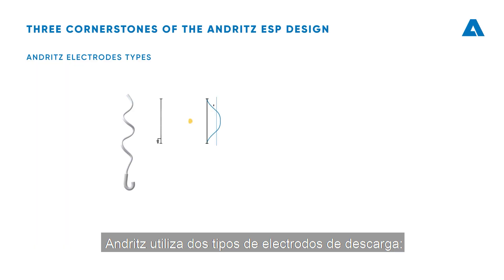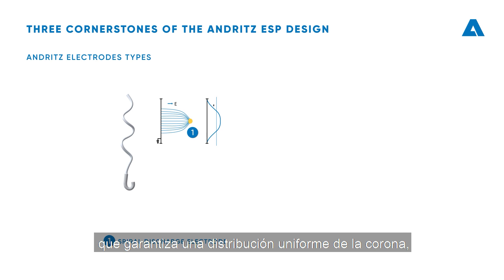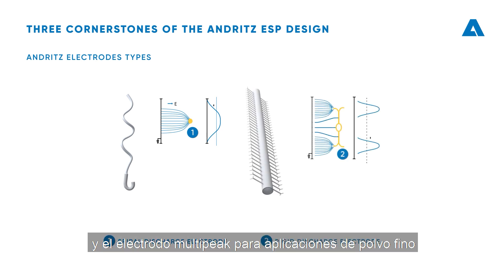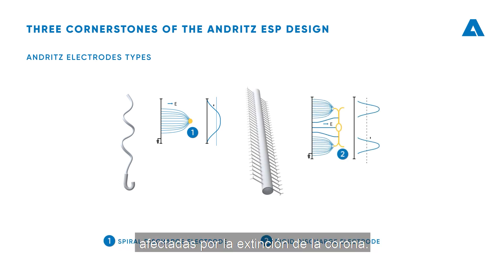Andritz employs two types of discharge electrodes: the cost-effective spiral discharge electrode, which ensures uniform corona distribution — especially important for high-resistivity applications — and the multi-peak electrode for fine dust applications affected by corona quenching.